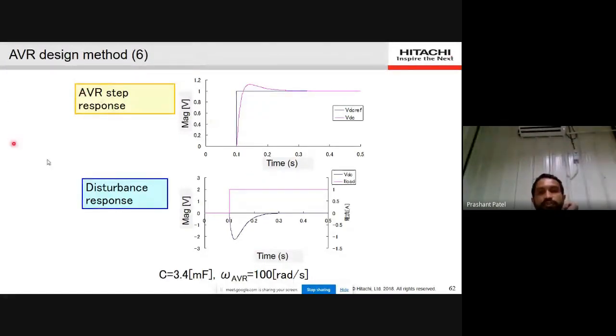Also check, suppose if you apply 100% load, the blue waveform shows there is a dip in the DC bus voltage. If you apply the step load, the pink waveform is the load current. So what is the dip? Is it within acceptable limit, because the DC bus voltage of the converter has a lower limit and upper limit. So think about whether we are achieving our criteria or not. If we are not achieving the criteria, we have to modify the gain.